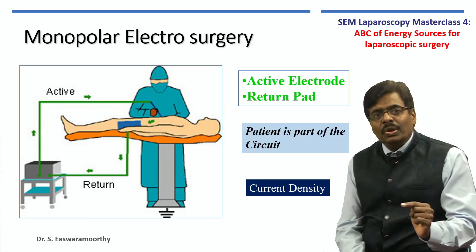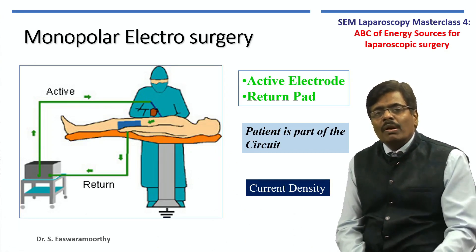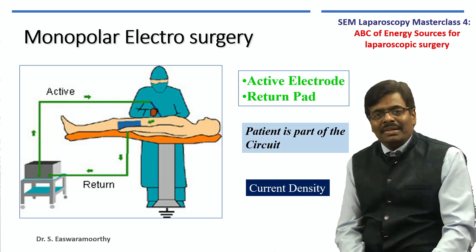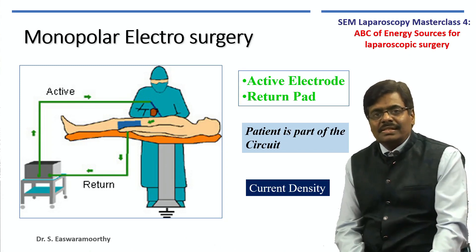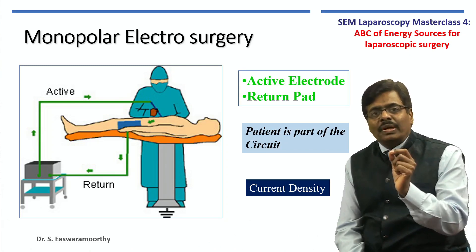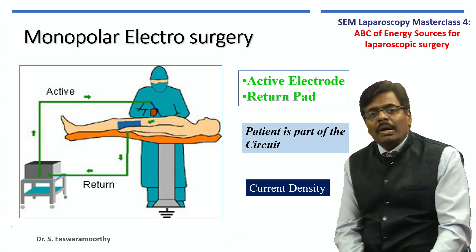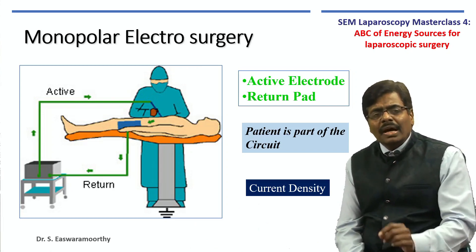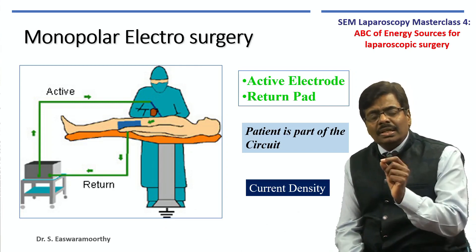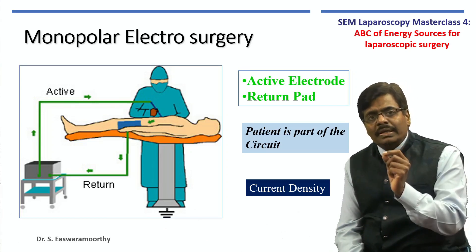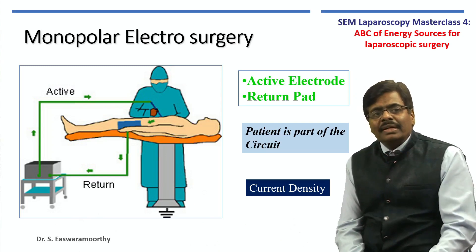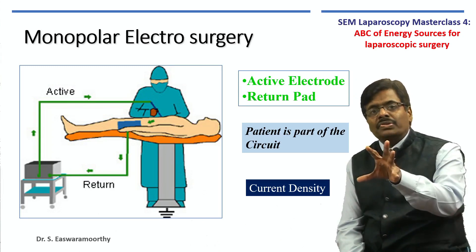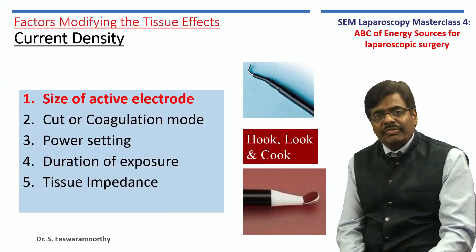The current reaches the return electrode pad, usually placed behind the patient's thigh, and from there returns back to the electrosurgical unit, thereby completing the circuit. The two basic important things about monopolar electrosurgery are: one, the current has to complete a circuit; and two, it always prefers the path of least resistance. The important terminology to understand is current density. The surgeon holds the active electrode where the effect is concentrated, whereas nothing harmful happens at the return electrode because the current is dispersed there. It is the current density that makes the difference.